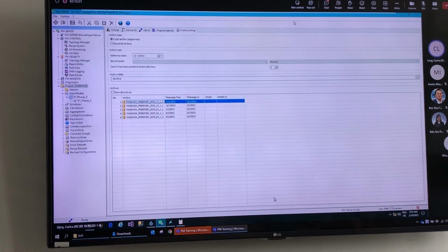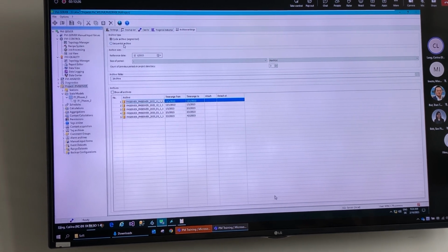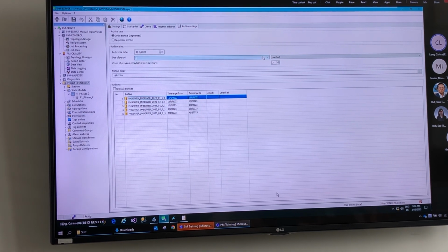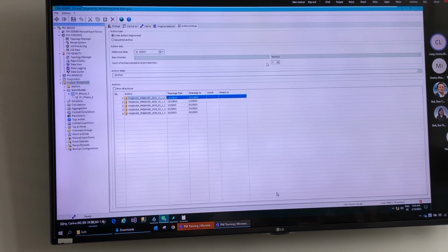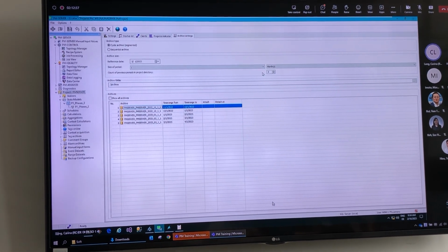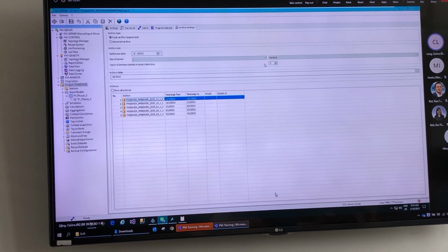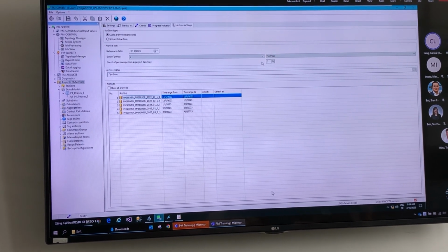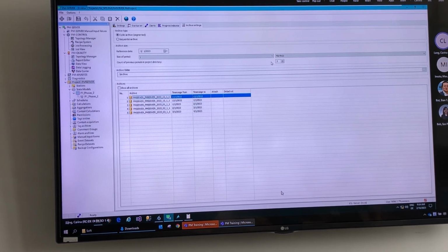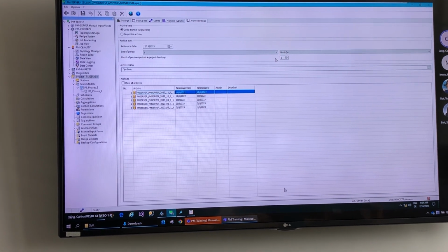But for that use, we recommend to select the archive type sequential archive, and then, for example, you can change the size of period or the count of previous periods. Then you can import the data because all of the databases are then available for your time range. And if you do not need them currently, then you can just detach this database and store it in the archive folder, so that you can attach it every time you need this information again.